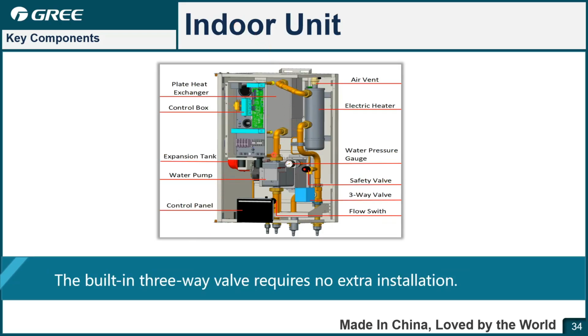For the hydro box, the indoor unit, here you can see the inner structure. The control panel is built in, and the water pump. This is the inverter water pump, expansion tank, control box. Plate heat exchanger, here, this one, and this is the air discharge for the air release, and this is the heater. Water pressure gauge, safety valve, three-way valve, flow switch here. So actually you can see for the split VERSATI 3, the three-way valve is built in. So for the project, no need to install another three-way valve. It is built in, so you can save some installation cost.